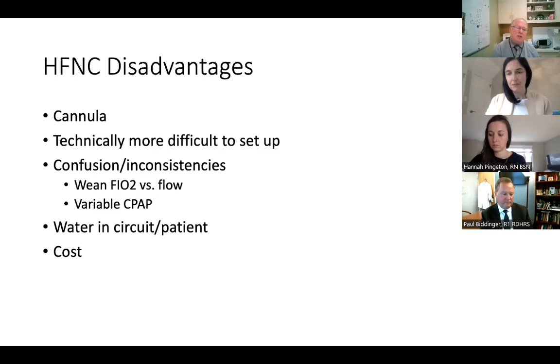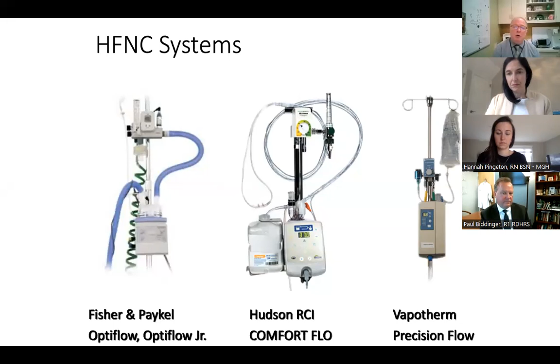The one we use here at Mass General is the Hudson RCI Comfort Flow System, but once again, they're all good humidifiers. They provide up to a 90 to 100% relative humidity at whatever temperature we set. And we don't set them at body temp. We don't set them at 37 like we do our ventilators. We set them a little bit lower than that because the upper airway is still intact. So there can be some heat and humidity added there. So we don't want to overheat them. But they all work pretty well the same.